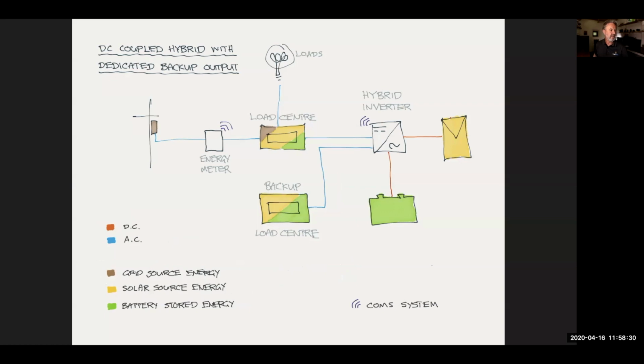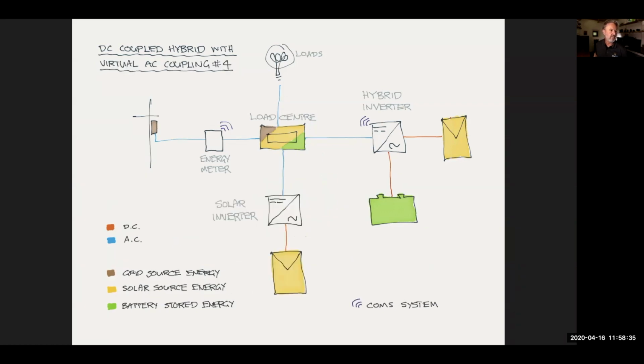That's the DC coupled system with a dedicated backup. Now, here's another one. You don't actually have to choose one or the other. You can have AC coupled and DC coupled. So here we've got an existing solar inverter system installed, the bottom inverter there, and the customer wants to add storage and they want to add more solar. So this is where they've added a hybrid inverter, and so they've effectively got both DC coupled and AC coupled systems in the same installation.